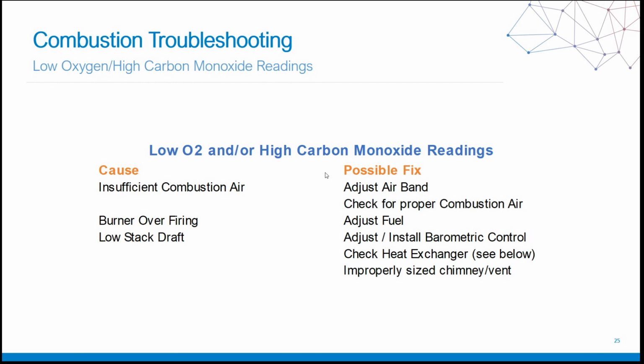One of the things we don't want to assume is that the technician that was there prior did everything perfectly. A lot of times that doesn't happen. Don't assume anything, because remember, the liability is large. The health and welfare of both yourself and the occupants ties back to you. So you want to make sure that you're checking that the flue pipe or exhaust venting is the correct size.